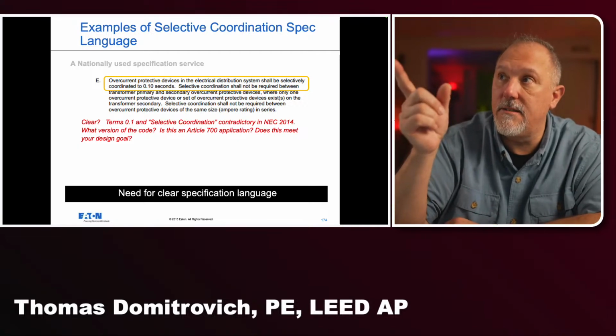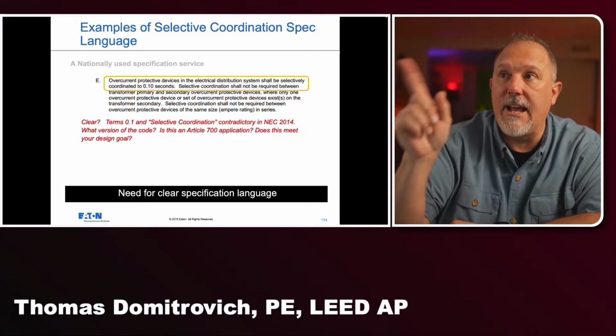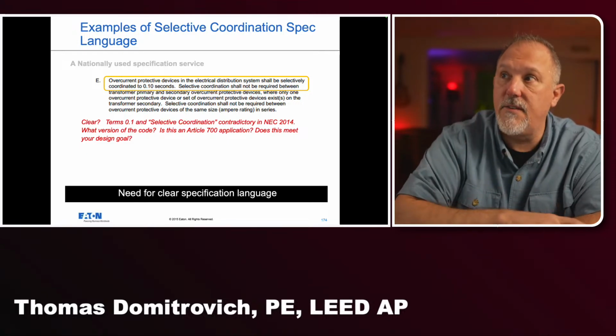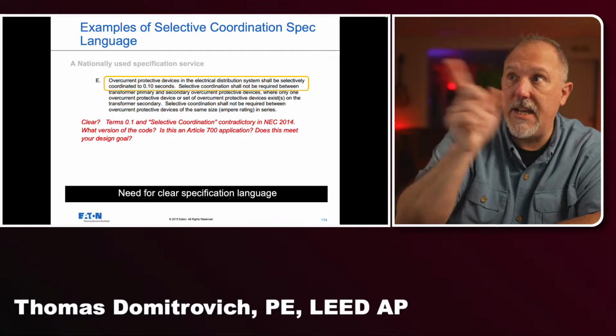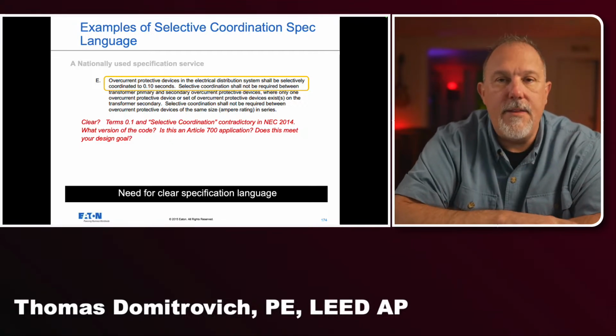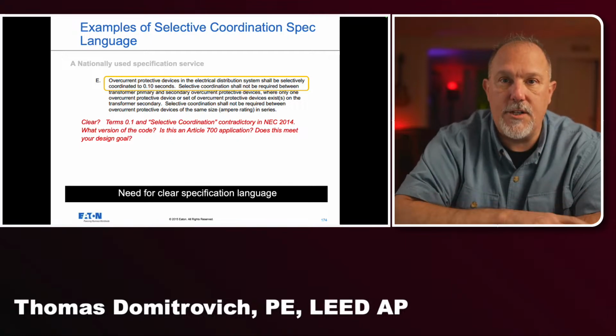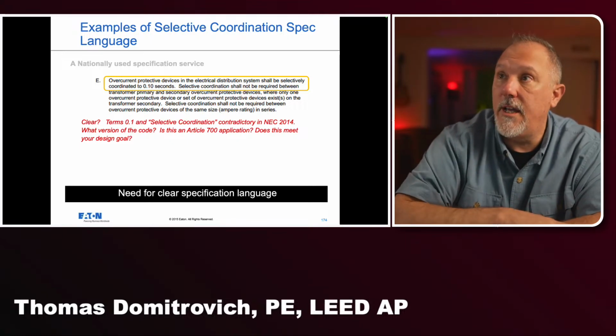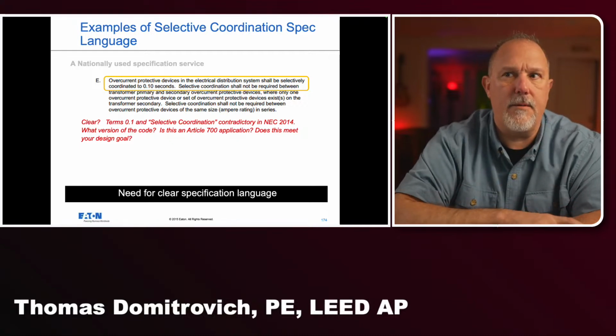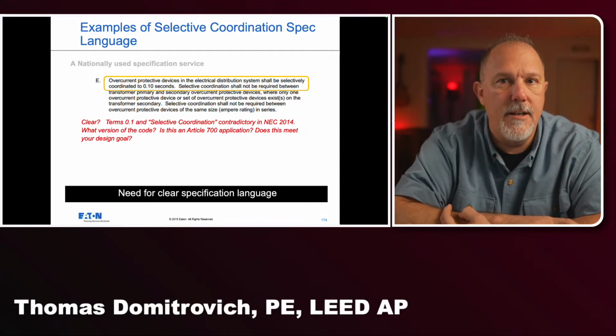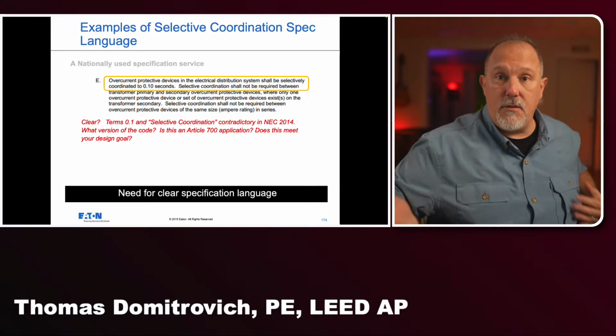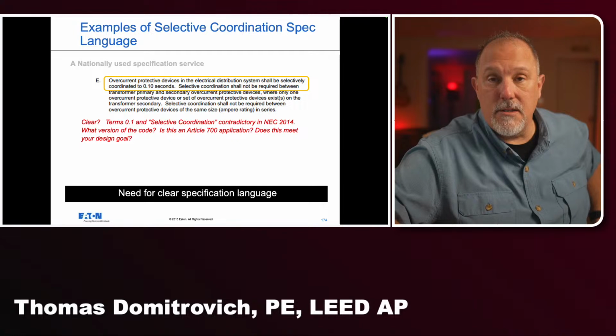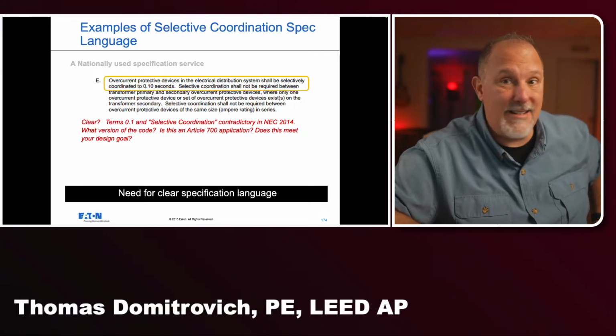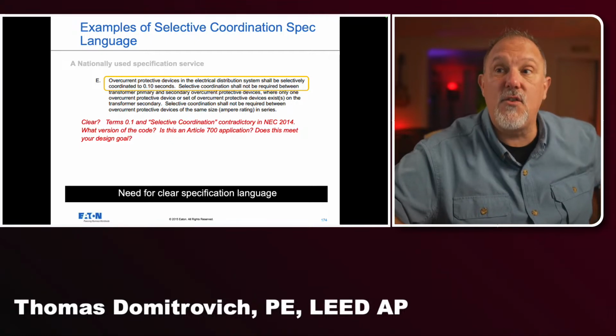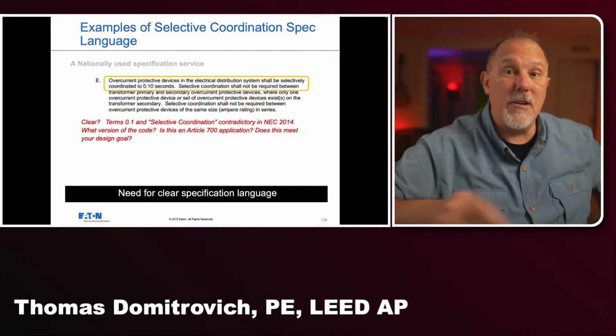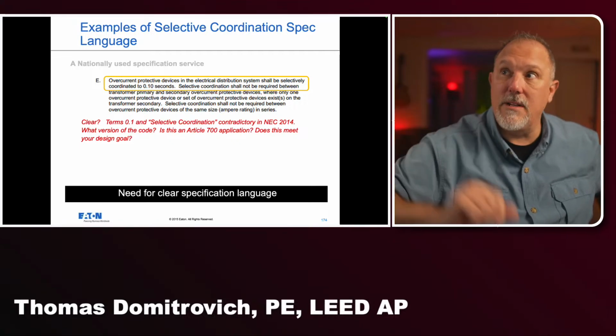Because if I quoted this and I gave you a 0.1 second coordination for an Article 700 system, and I met your spec, and the inspector came by and said, ask the right questions, and you said, well, it's selectively coordinated at 0.1 seconds, and the inspector went, well, 0.1 seconds is not selective coordination, and you went back to the supplier, the manufacturer who gave you the quote, and you installed the system, you're going to find out, more than likely, it's not selectively coordinated. It has never been evaluated to any fault current for coordination whatsoever, because it's a 0.1 second system.